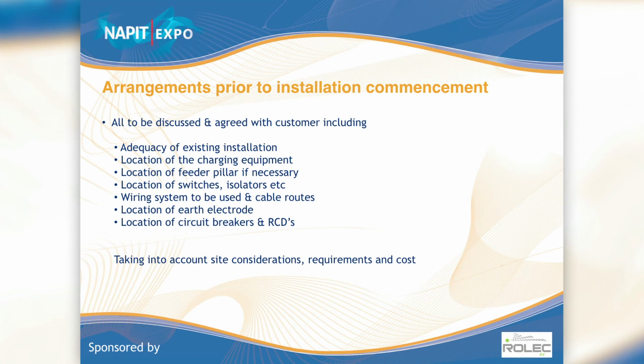If the supply authority neutral goes down on a TNCS system, the voltage on the earth will increase. And if it increases on the earth and you touch it, it's going to hurt. So there's a problem with the earthing systems being as they are today. We'll come to that in a second. You also need to make sure that the existing installation is adequate. It's no good having an installation that is 50 amps and you've only got a 60 amp supply in it, and then you're going to put another 32 on it. It won't have it. You've got to make sure that the charging equipment is put in the right place. There may be other switches that you're going to put in place, isolation switches. If it's on the outside of a garage, you don't want next door tapping into it, so you would put an isolator in the garage to make sure nobody else can nick your electric.